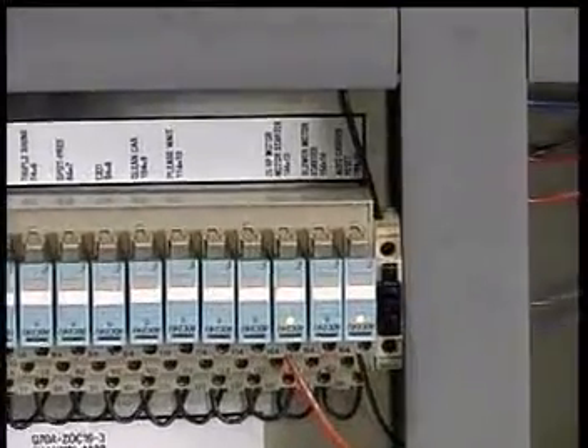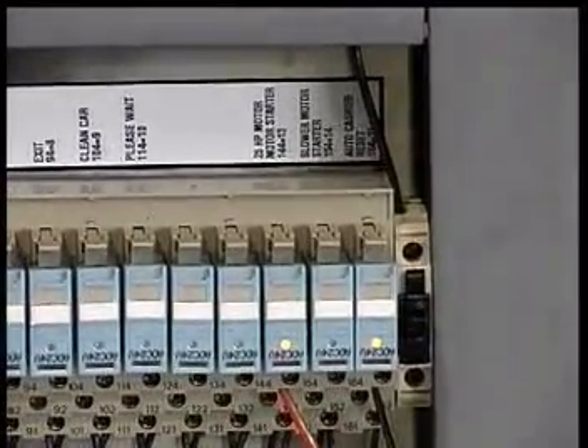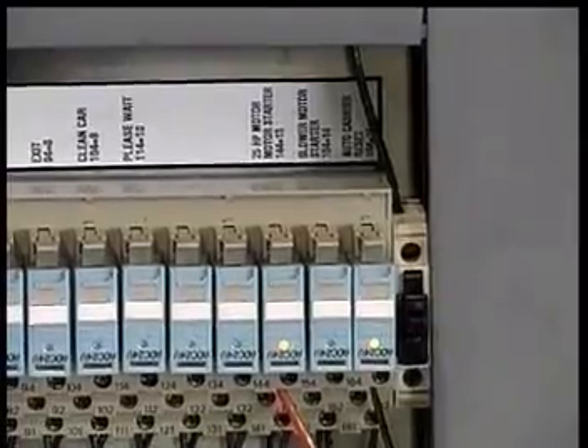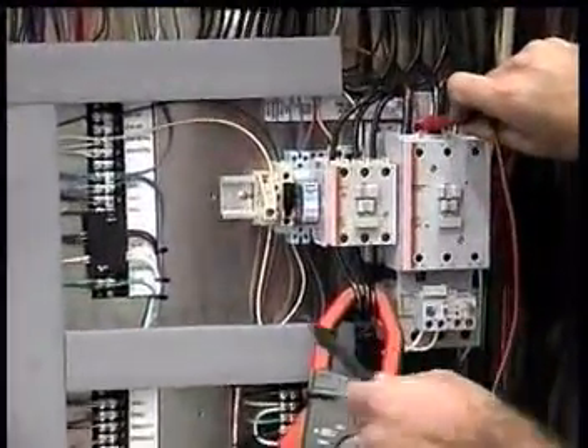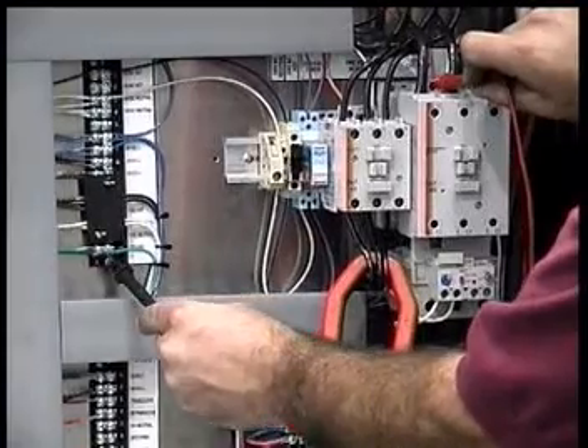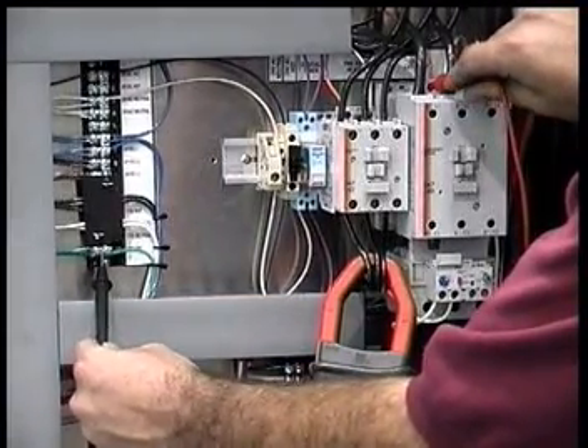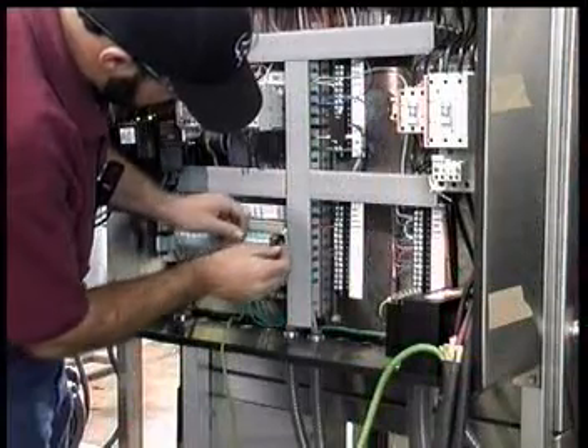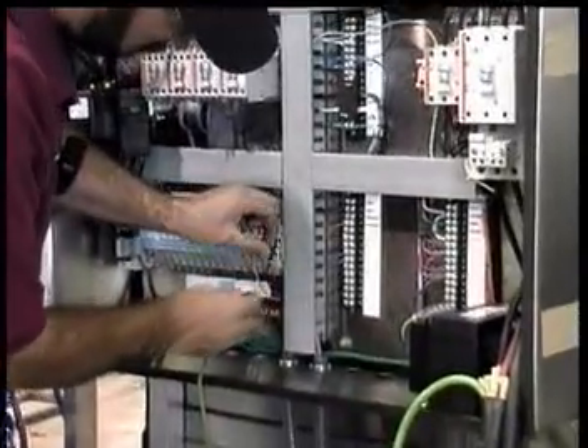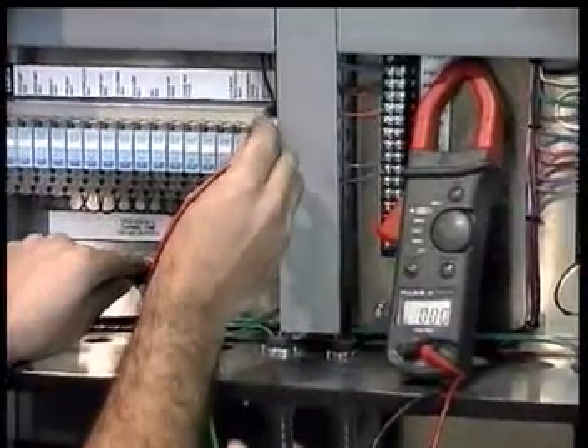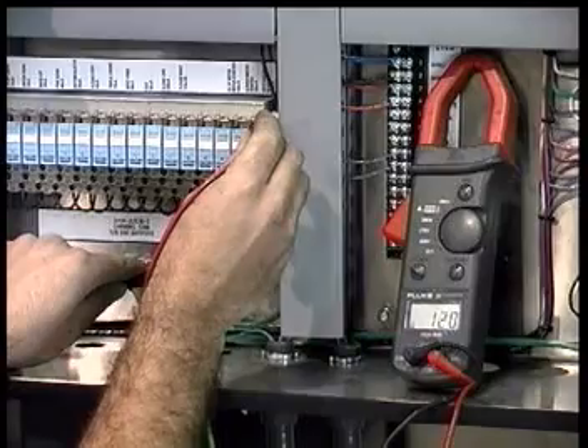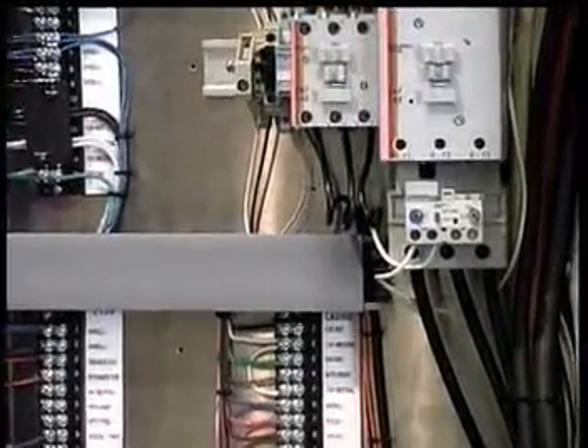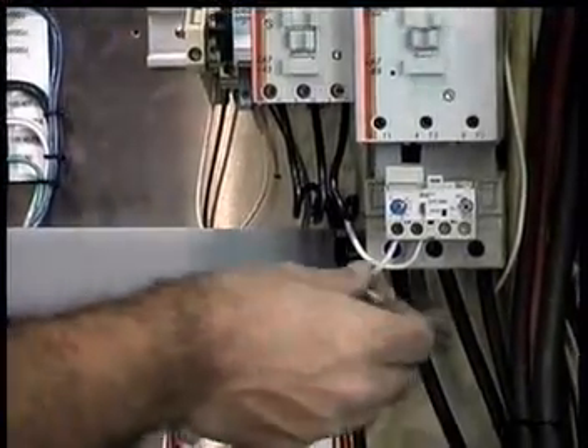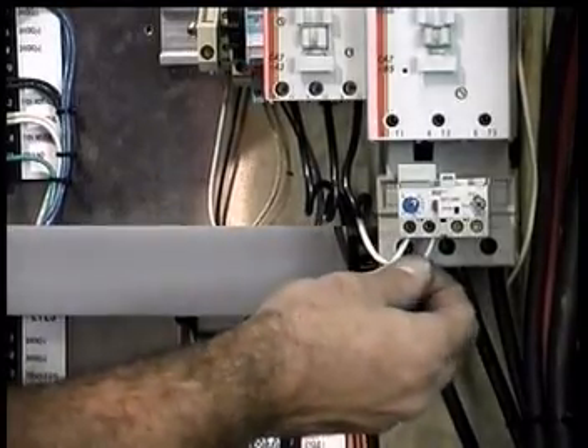If the overload is not tripped and the starter does not pull in and you have a signal light on the starter relay, check for 110 power between the A1 terminal on the top of the starter and ground. If there is no 110 volt power, check the fuse on the ZOC16 relay card and verify 110 power on the top and bottom side of the fuse housing. If 110 power is present, check for a loose neutral wire at the starter.